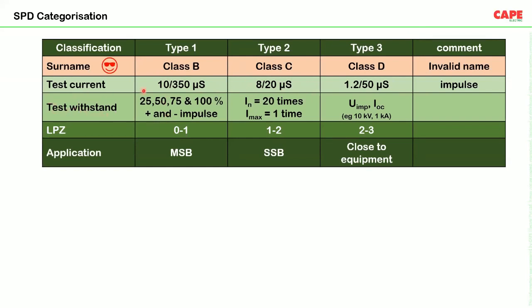Now, type 1 SPD, how is it tested? With 10 by 350 microsecond current. Imagine you have a 10 kiloampere type 1 SPD, 10 by 350. That means the SPD is tested at 25% of its rated current, which is 2.5 kA, 50% of its rated current, 5 kA, 75%, 7.5 kA, and 100%, 10 kA. Positive and negative impulses are applied to the device, and the device must be able to withstand. These devices are suitable for lightning protection zone 0 to 1, between zone 0 and 1. These devices must be installed in the main switchboard.